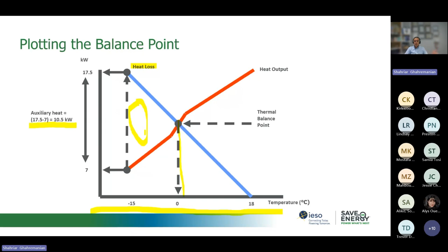The area on the left hand side of the balance point is the time when we need to shut down our heat pump and run a supplemental heat system, whatever system we have here. For example, in here, what I calculate is that we need an auxiliary system of 10 or almost 11 kilowatts for this specific situation in this example. So when you're talking to a designer or a contractor, make sure they provide you the balance point for your facility, design the heat pump system based on that, and let you know how much extra supplemental heat you need during the very cold days.